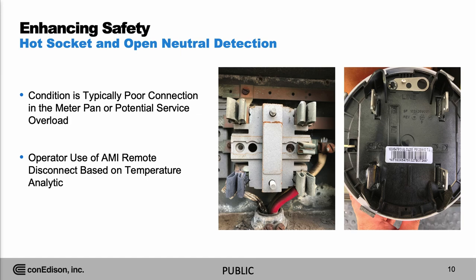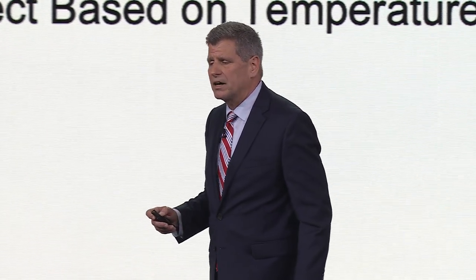We have developed analytics with the C3 application to give us advanced warning of these alarms, and we put them into a monitoring phase where our operators continuously review these problem meters. We leverage the C3 application to scan meter temperatures every 2 hours and monitor to ensure the issue is resolved. Just last year alone, we were able to detect over 300 hot socket alarms.